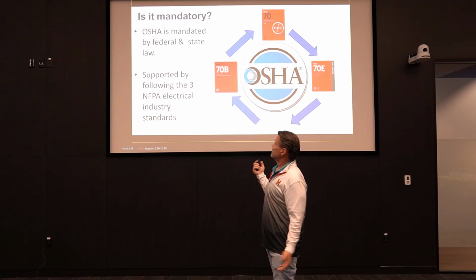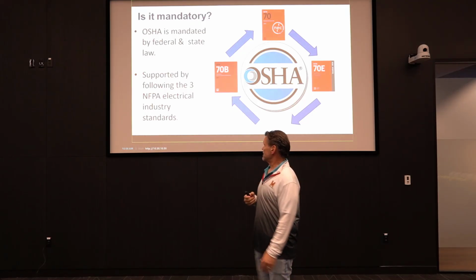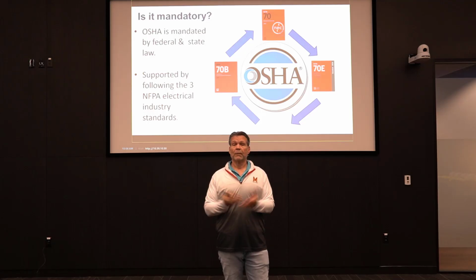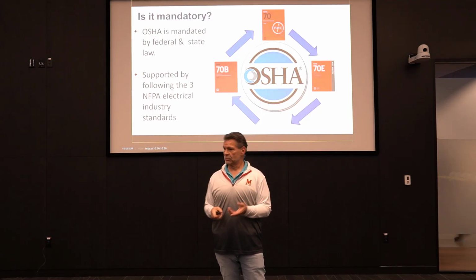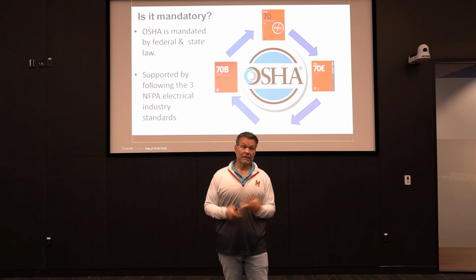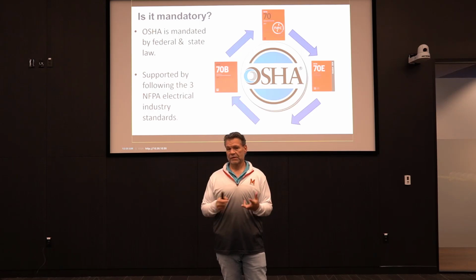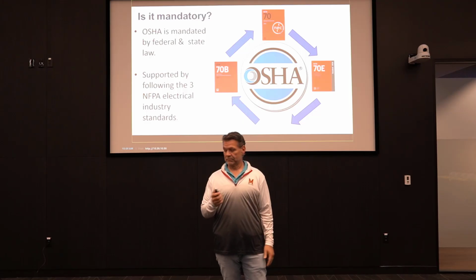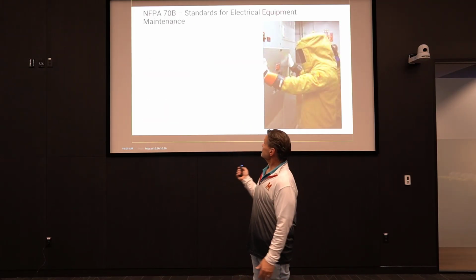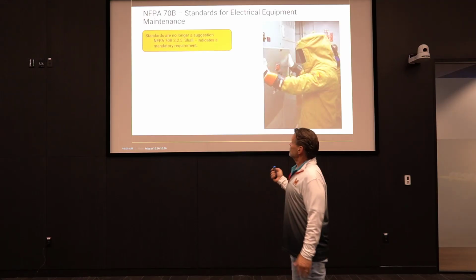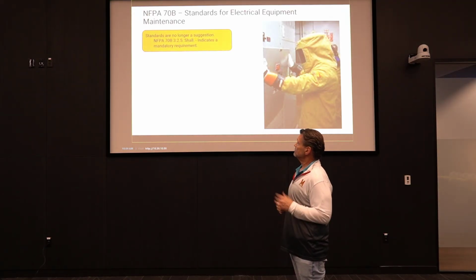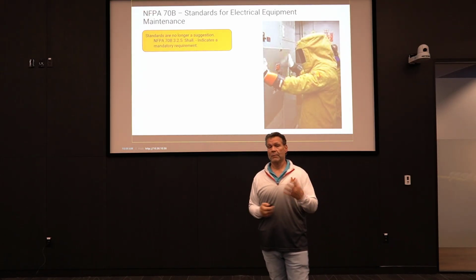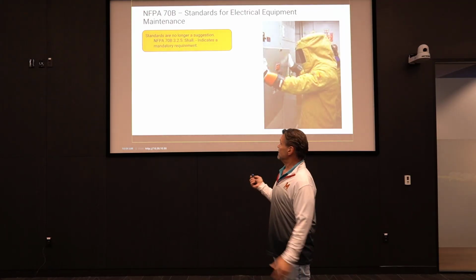So is it mandatory? OSHA is mandated by federal and state law, and then it's supported by our three main books that we use: NFPA 70, National Electric Code; NFPA 70E, Standard for Safety in the Workplace; and then NFPA 70B now is another one, Maintenance of Equipment. So standards are no longer a suggestion. NFPA 70B shall. So shall means it's a mandatory requirement. Now we need to follow NFPA 70B.